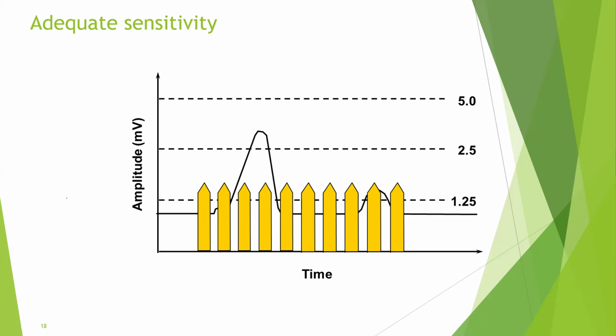Maybe here in this example, 1.25 or 1.5. So the device here is capable of detecting what you want it to detect, which is the intrinsic ventricular depolarization. And you have hidden the repolarization, and you have even hidden a P wave if the patient had far field sensing. For example, if the ventricular lead is very close to the atrium, it can see what we call far field, meaning there is a wave coming from afar and detected by the lead polarity. So it sees a P wave, but in a very small amplitude. And if you increase the sensitivity adequately, the lead will not see that far field P wave.